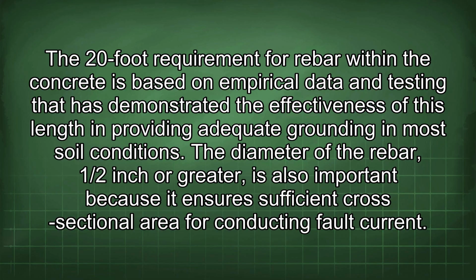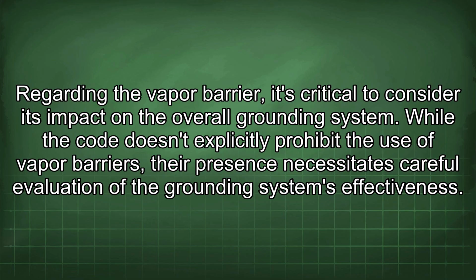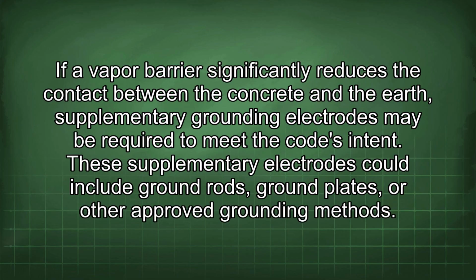fault current. Regarding the vapor barrier, it's critical to consider its impact on the overall grounding system. While the code doesn't explicitly prohibit the use of vapor barriers, their presence necessitates careful evaluation of the grounding system's effectiveness. If a vapor barrier significantly reduces the contact between the concrete and the earth, supplementary grounding electrodes may be required to meet the code's intent. These supplementary electrodes could include ground rods, ground plates, or other approved grounding methods.